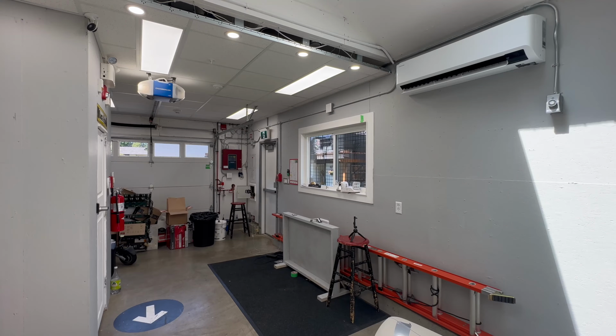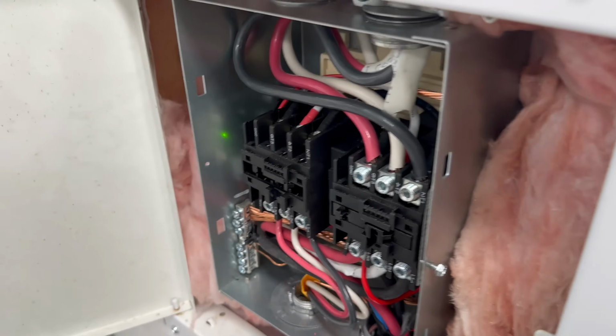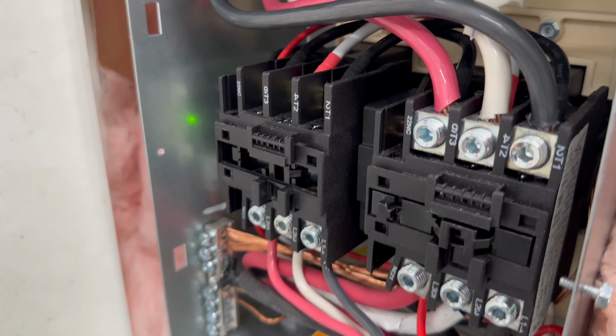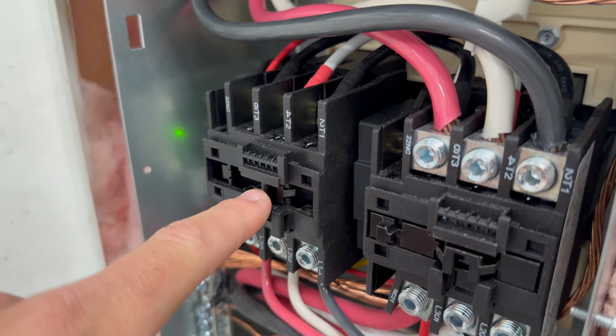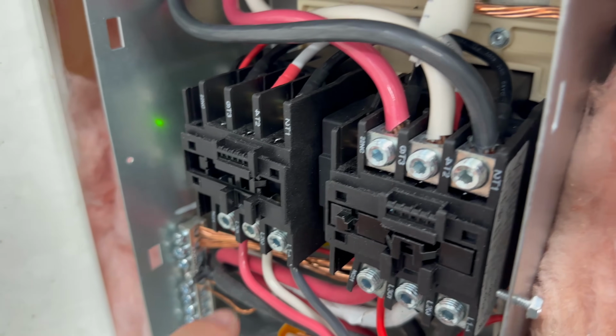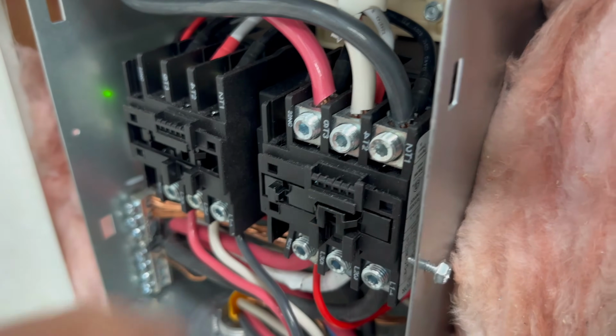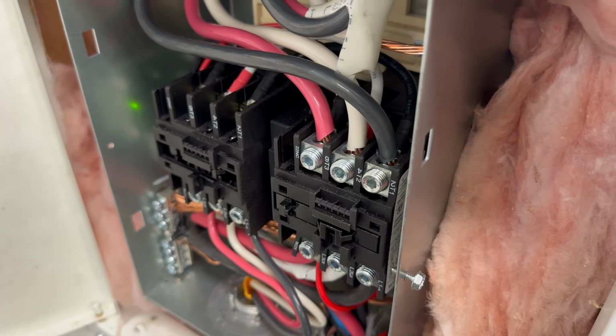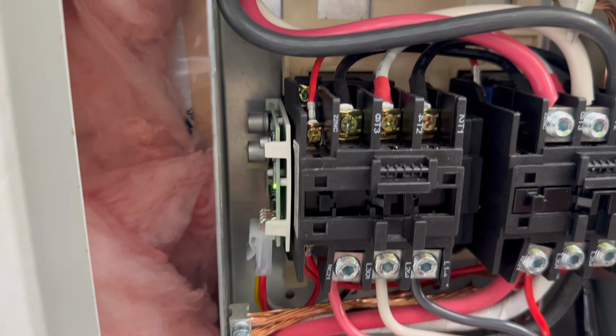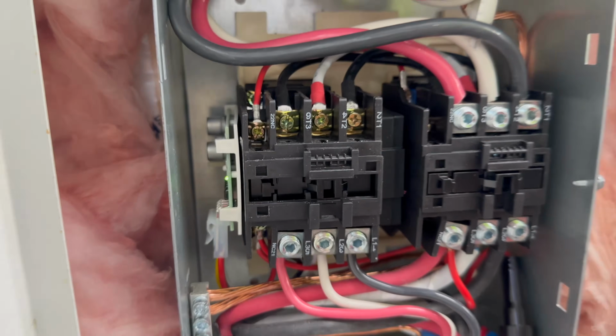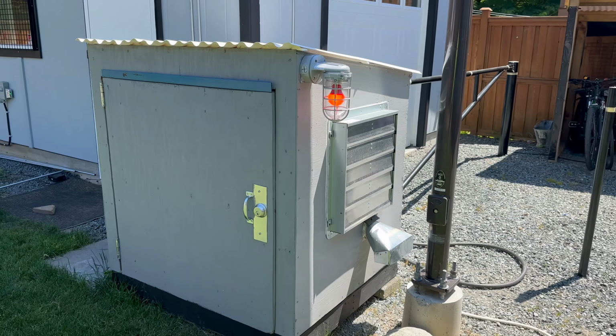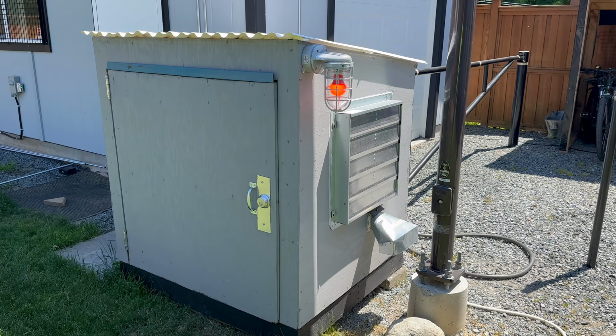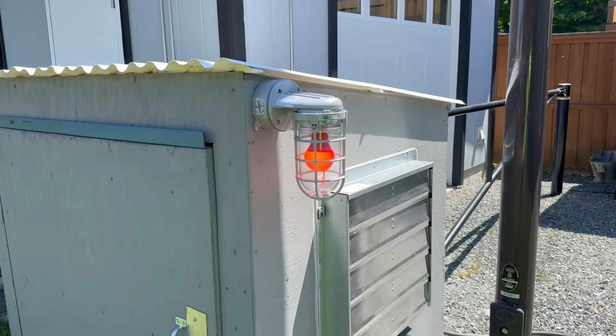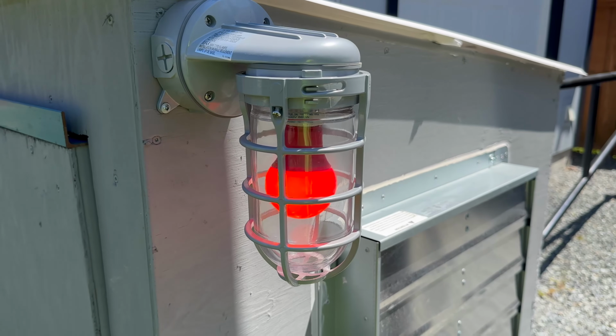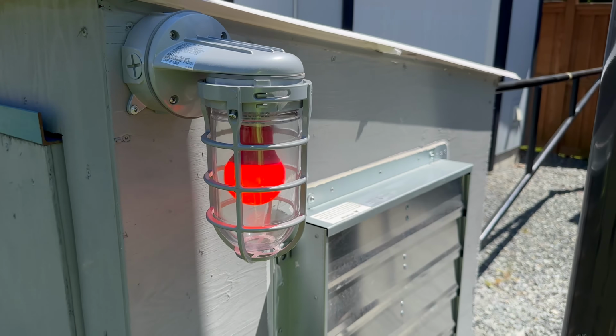This building is now being powered off of generator power. Now that we're powered off of generator power, you can see that this contactor has now pulled in, so that means we're powered off of generator, and the BC Hydro contactor has let go to make sure that you don't get any backfeeding. Green indicator light on the side shows that we are powered off of generator. And here is the generator running outside. Our power indicator light is on, showing that the generator is running.